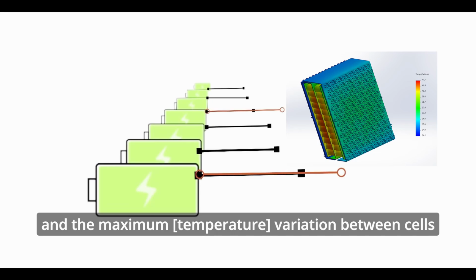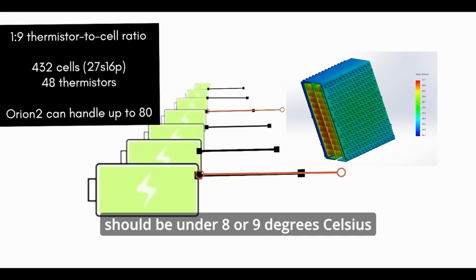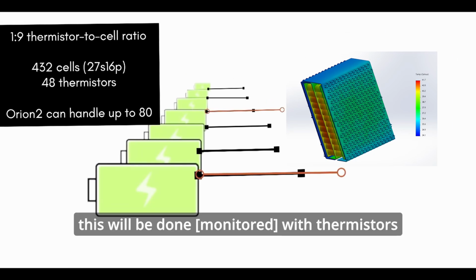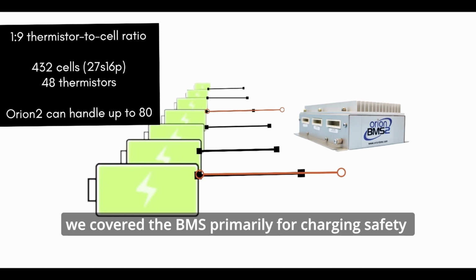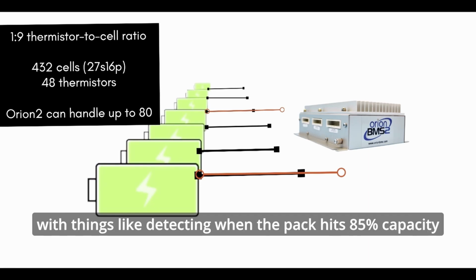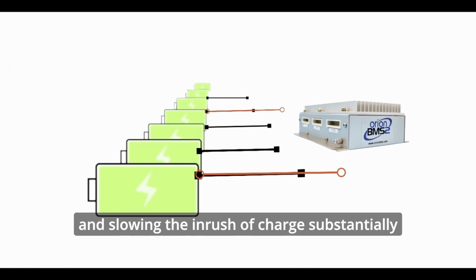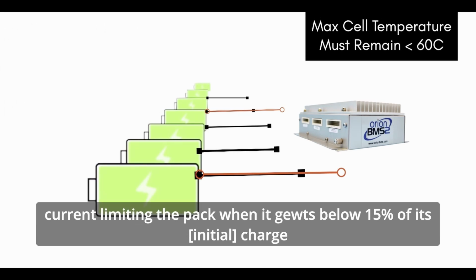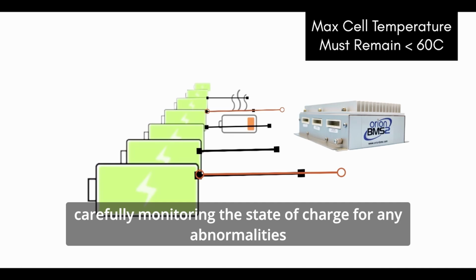And the maximum variation between cells should be under 8 or 9 degrees Celsius. This will be done with thermistors, about 1 per 9 cells. We covered the BMS primarily for charging safety, with things like detecting when the pack hits 85% capacity and slowing the inrush of charge substantially, current limiting the pack when it gets below 15% of its charge, carefully monitoring the state of charge for any abnormalities.